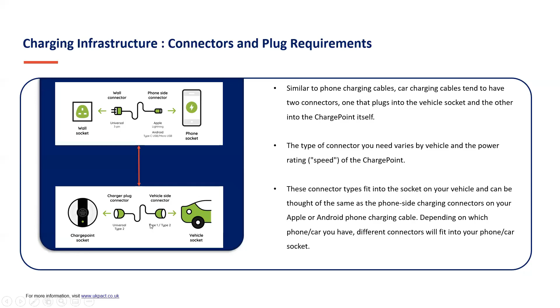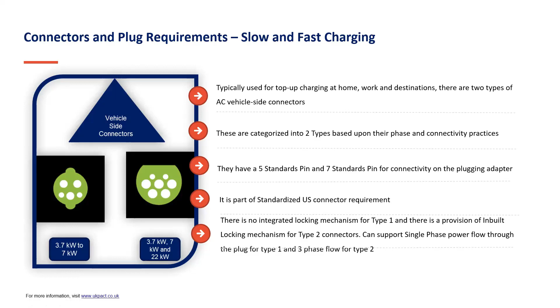On the vehicle side, this is the Type 2 connector. As you can see, the earlier sockets for 3.7 to 7 kilowatts have 5 pins, and the Type 2 has 7 pins. In the 7-pin socket, there are 3 pins for the 3 phases, a protective earth, a neutral, and 2 on top which are communication pins. One is called CP and the other PP, the communication pilot and proximity pilot. These pins establish the connection of the vehicle's controller with the charger's charge controller, and that's when the information exchange and handshake happens.